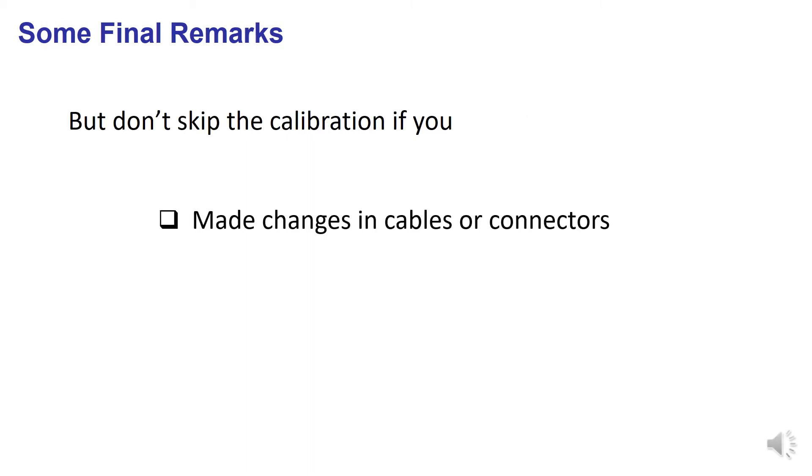You can save the calibration parameters to reduce the number of times you do a calibration. But a new calibration is especially important if you have replaced, cleaned, or repaired cables or connectors, or you notice significant changes in the environmental conditions, like humidity or temperature changes.